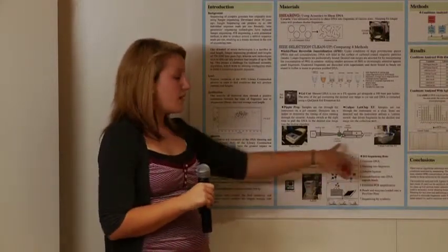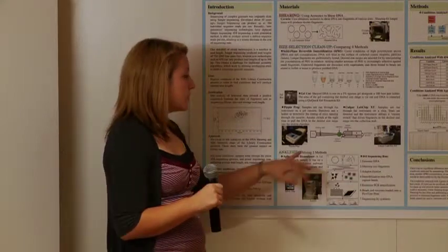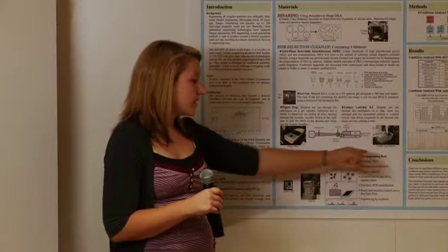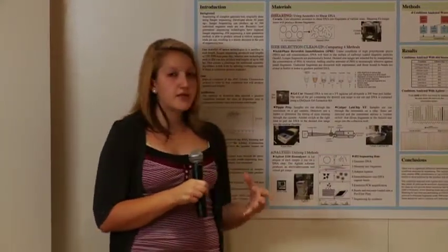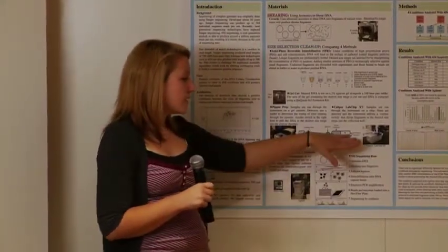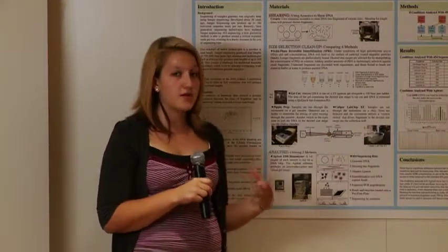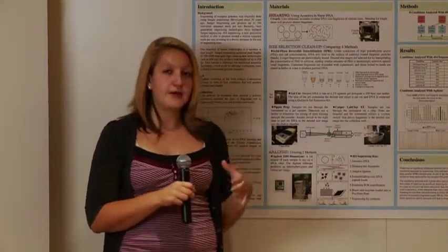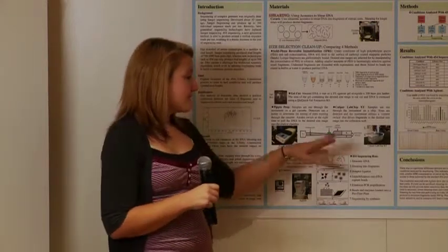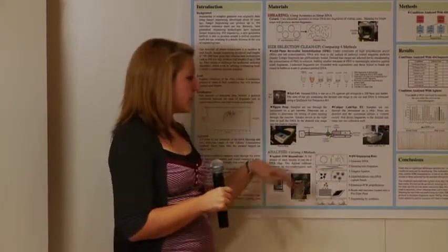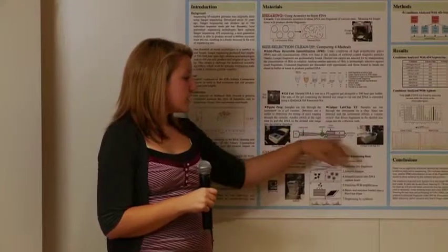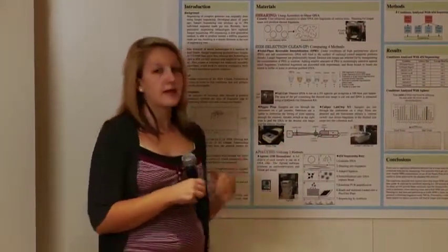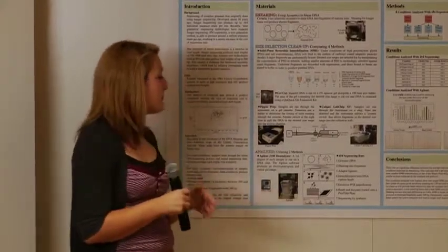And they both work on this basic principle, where you load your DNA into a loading well, and on the other end there are switchable anodes. So originally the DNA is flowing toward a positive charge in the waste chamber, and then a detector, which works with an internal ladder in the machine, tells when 500 to 800 base pairs are flowing through, and it will switch and pull the DNA into an elution chamber, and you can just pipette out the DNA and it'll be the size range that you want.